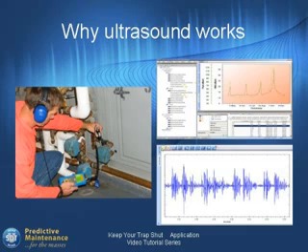With the SDT 270, you can choose to listen to the trap and, using your experience, judge its condition. Log decibel levels of each trap and store them to a database that will compare and alarm changes from month to month. Log temperature levels upstream and downstream of the trap and store them to the same database. Capture a dynamic signal of the trap and visualize its performance in the time domain, while comparing to previous months' time signals.